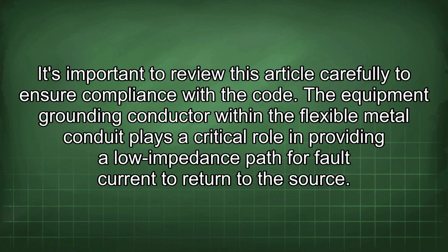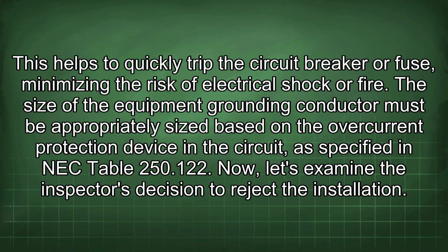The equipment grounding conductor within the flexible metal conduit plays a critical role in providing a low impedance path for fault current to return to the source. This helps to quickly trip the circuit breaker or fuse, minimizing the risk of electrical shock or fire. The size of the equipment grounding conductor must be appropriately sized based on the overcurrent protection device in the circuit, as specified in NEC Table 250.122.